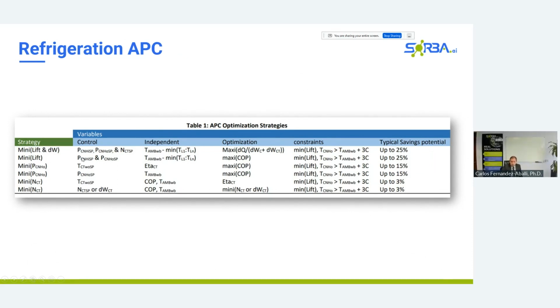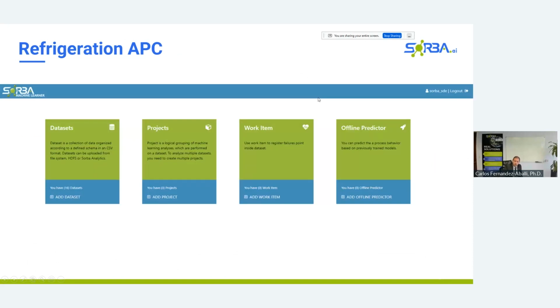In some systems, you'll be able to control your discharge pressure, your suction pressure, and the speed of the fans in the cooling tower. In other systems, it'll be just your suction pressure and discharge pressure. In other systems, it'll just be fan speeds and pump speeds. It depends on what you can control in each system. And then there are more adequate optimization independent variables and metrics for each of these control strategies. And of course, they have different saving potentials.